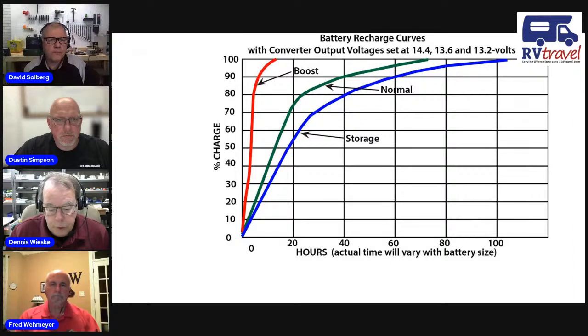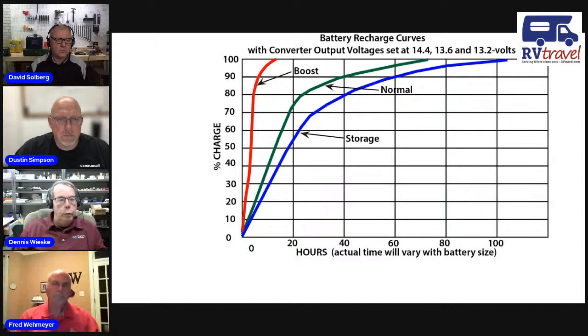Part of charging too is the differential voltage between the battery and the converter. You need a higher charging voltage than the battery voltage in order to allow current flow. The battery has internal resistance, the wire has resistance, those add up plus the current. The higher the differential, say at 14.4 in a boost charge, the charge rate is going to be much more rapid than at a normal charge rate of 13.6 volts, or a storage charge rate of 13.2.